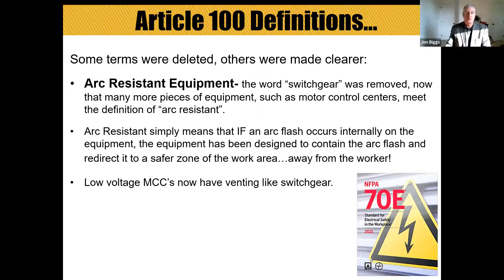If an arc flash would occur in an arc resistant motor control center, the equipment has been designed to contain that arc flash and redirect it, usually through venting on the sides or out the back, to a safer zone away from the worker in their work area. For years, actually decades, switchgear has been designed this way, but most low voltage equipment was not. Now we're seeing low voltage equipment that is arc resistant. So that's why they made the change to just the terminology arc resistant equipment.